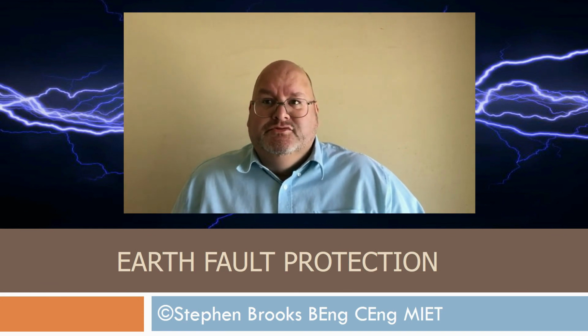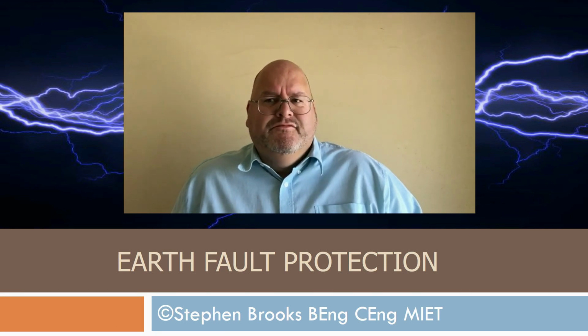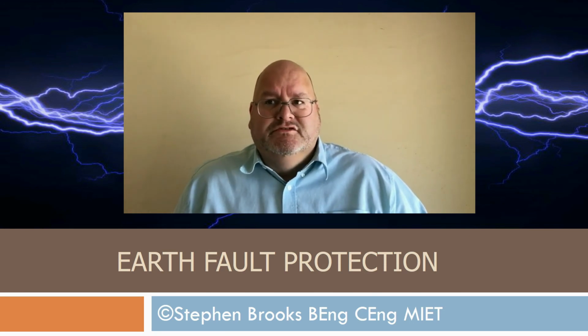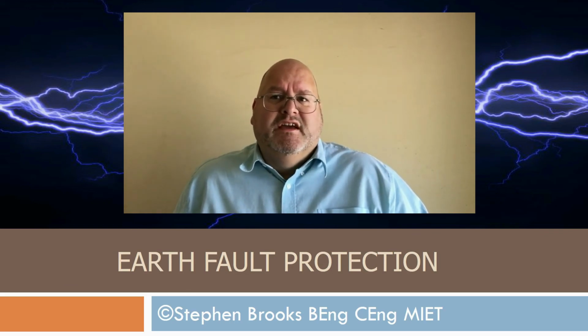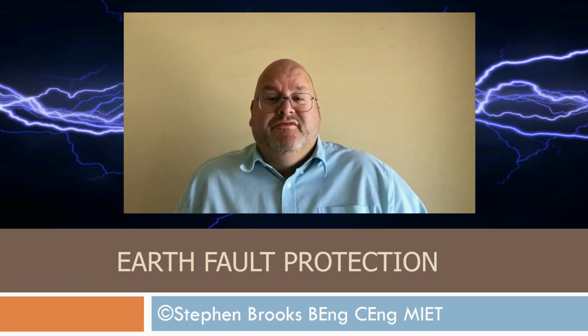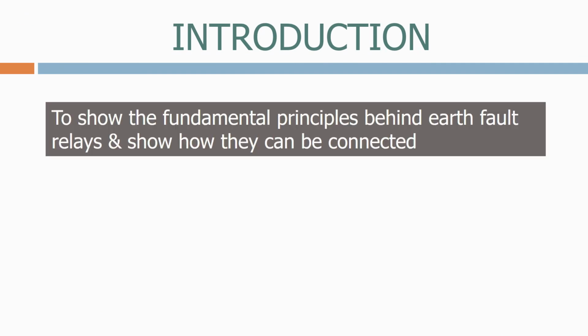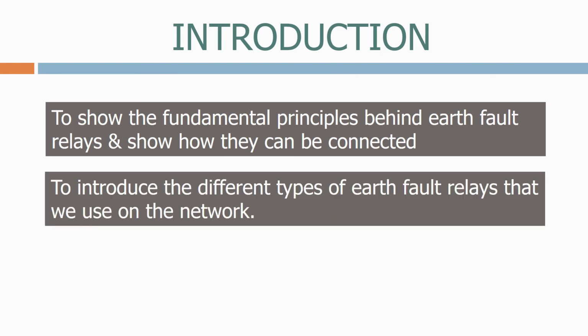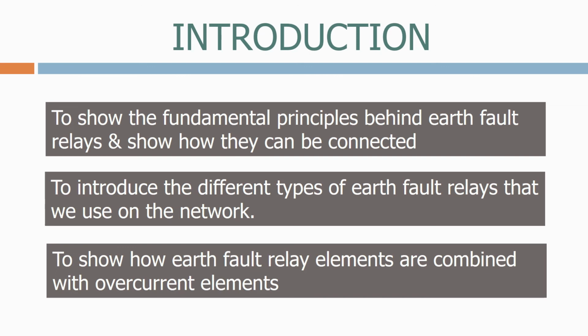Congratulations for making it to the final module, which covers earth fault protection. Earth fault protection operates in a similar manner to overcurrent protection, so the principles behind this course should be easy for you to understand. Although the specific ways in which we connect earth fault relays to the current transformers needs to be fully understood to make the principles clear.